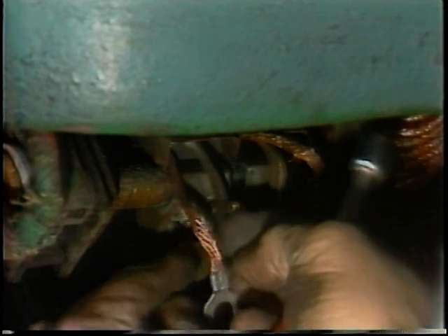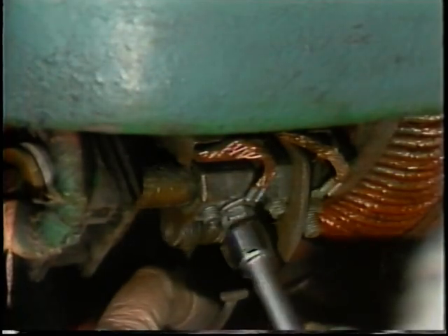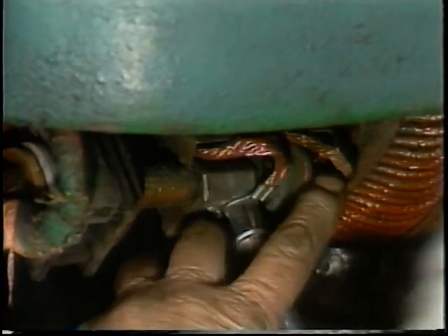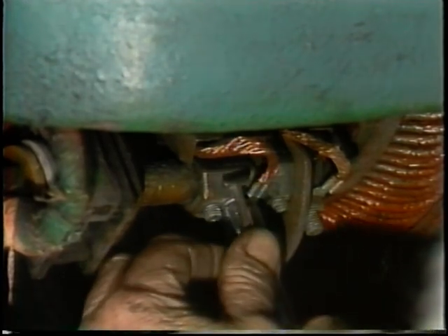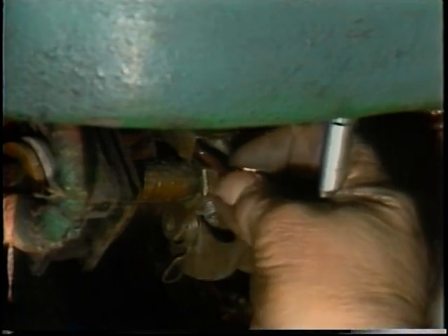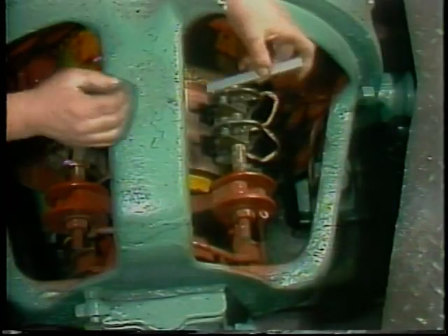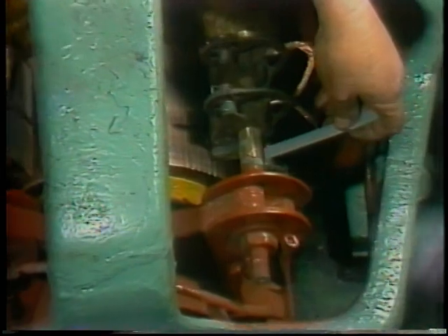Use brushes of the right hardness grade for the motor. Be sure the new brushes go in so that the bevel on the end, if there is one, matches the commutator, and that the brushes fit properly in their holders. They should be free to slide in and out, but must also be held snugly so they cannot chatter or wear crooked. Check the specifications to make sure the brush holder is the right distance from the commutator. Adjustment may be necessary if the commutator has been turned down or if the brush holders have been moved for any reason.